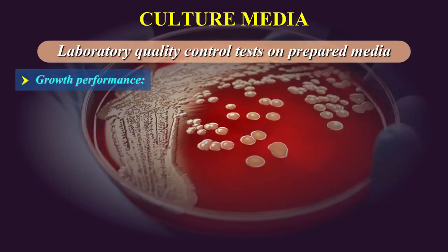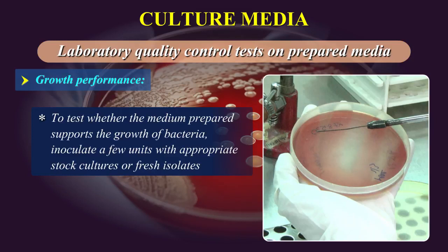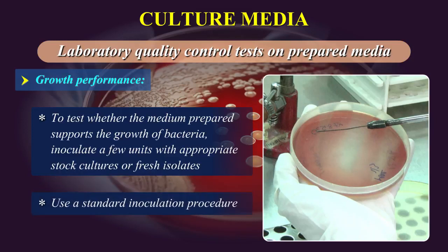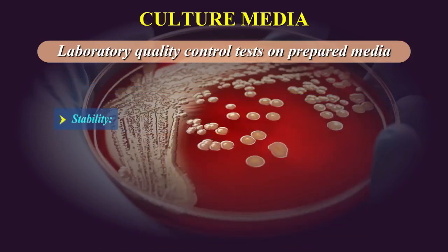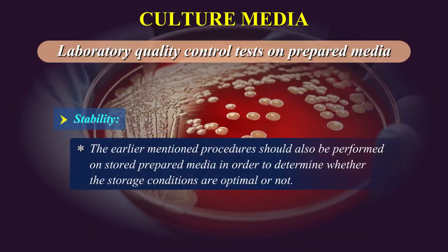Growth Performance: To test whether the medium prepared supports the growth of bacteria, inoculate a few units with appropriate stock cultures or fresh isolates. Use a standard inoculation procedure. For testing new lots or batches of media, inoculate old and new lots together and compare the performance of the two lots side by side. Stability: The earlier mentioned procedures should also be performed on stored prepared media in order to determine whether the storage conditions are optimal or not.